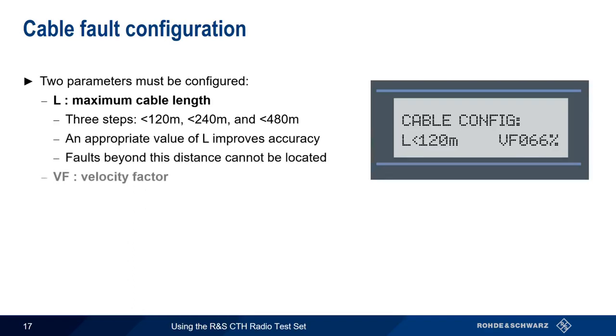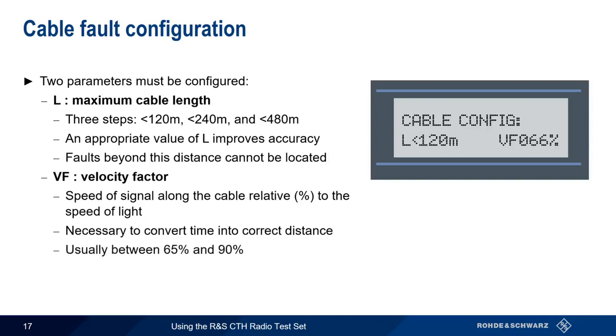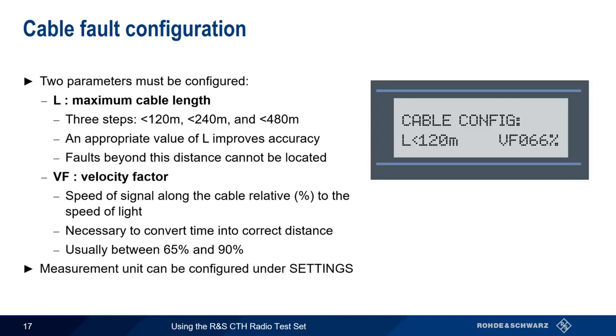The second mandatory parameter is velocity factor. This represents the speed of the signal through the cable under test, specified as a percentage of the speed of light in a vacuum. Velocity factor varies between cable types, so it must be given in order to convert time into the correct distance along the cable. This value is usually somewhere between 65 and 90 percent, and can usually be found on the cable datasheet. Note that the measurement unit can be switched between meters and feet using the Settings menu.